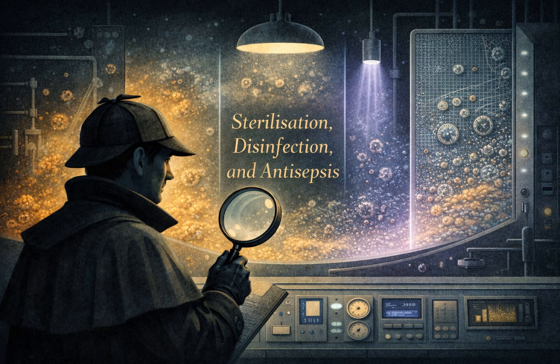Okay, let's drop down another level. Intermediate level disinfection. This is for surfaces or items that might touch intact skin or have accidental contact with bodily fluids. The key litmus test here, the bug we measure it against, is Mycobacterium tuberculosis. Why TB? Because, as we talked about with the pyramid, TB is the hardest non-spore-forming bacteria to kill because of that waxy cell wall. So if a disinfectant is proven to be strong enough to kill TB, we classify it as intermediate. This category covers your alcohols, your iodophores, and your phenolics.